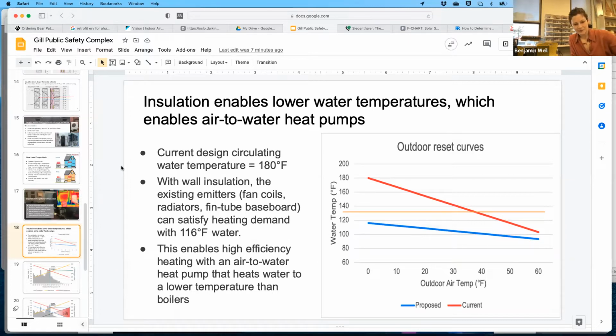And you can actually bring your water temperature down to 116 degrees. So this enables high efficiency heating with an air to water heat pump that heats water to a lower temperature than boilers. And the thing with heat pumps is the lower temperature, the smaller of a temperature lift they have to do. So basically, the less of a difference there is between the outdoor air temperature and the supply water temperature, the more efficient they are.